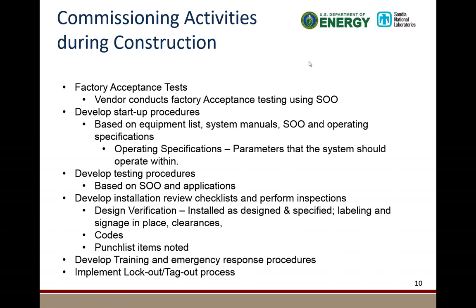Making sure the labeling and signage is in place. A lot of times you get to the end and there's no signage anywhere, and that causes a delay. It's also a safety concern if you don't know where things are fed from and you don't know what things are called. Make sure all your clearances, you should have your authority having jurisdiction come through. Make sure everything is installed per code.